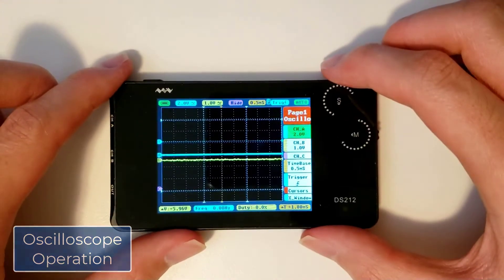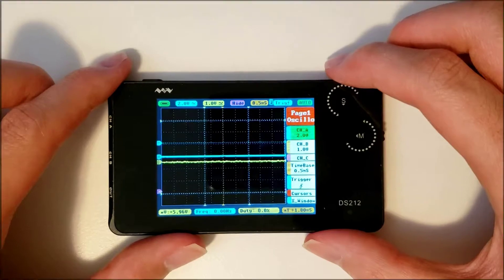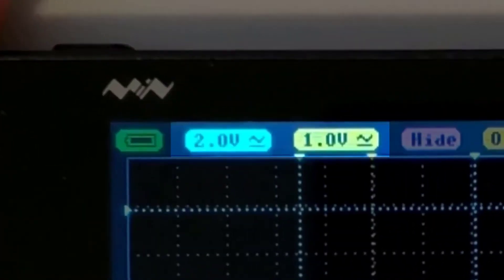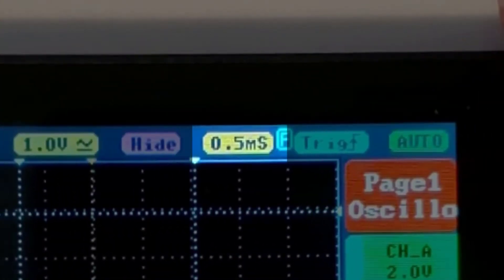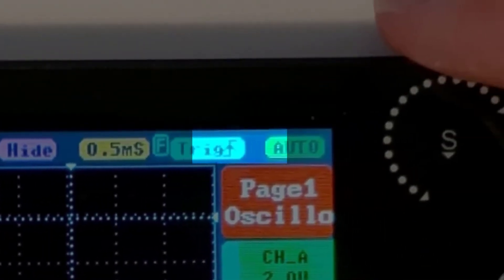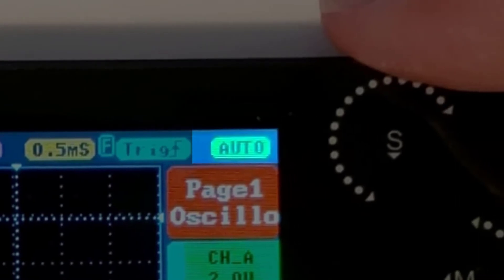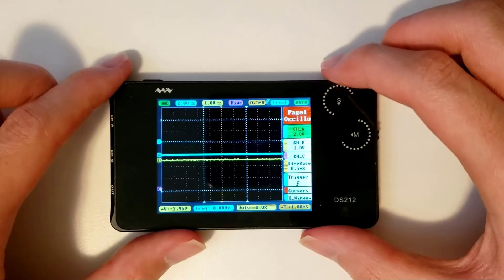You can notice a few boxes at the top here. Starting from the left, the boxes show the voltage divisions of the two channels, time division, trigger mode, and sync mode. All of these are important parameters, but how do you change these?